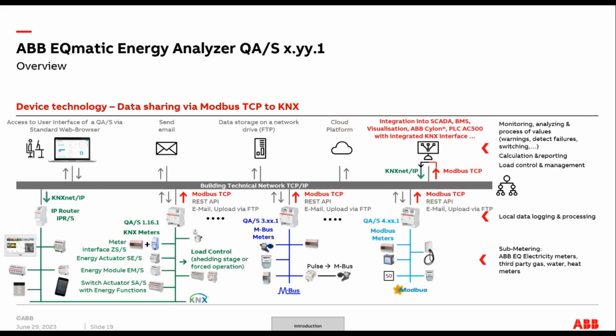Finally, because we have integrated into SCADA, BMS visualizations, Cylon, PLCs, whatever we have integrated, these can manage and control KNX devices. So from these head-end pieces of software, we can have logic control, load shedding, all the sort of stuff we want to do in the building, and we can fire KNX commands back onto our network, and using that, we can control whatever we want to do.